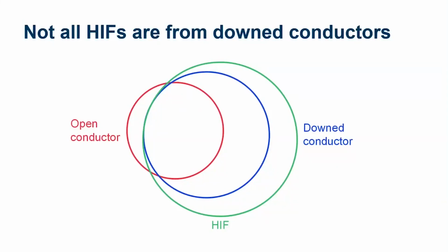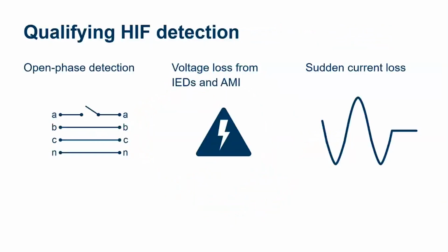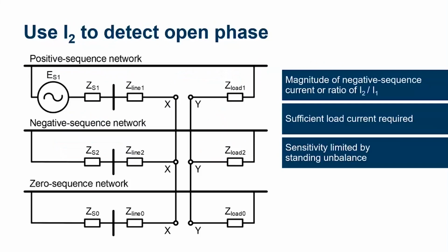So one of the things that we can do in order to give ourselves a higher degree of confidence that a high impedance fault is associated with a downed conductor is add another qualifying condition. We can look for an open phase by looking at our sequence components. We can look for an open phase condition based on voltage loss from other downstream IEDs or AMI metering, or we can look for a sudden loss of current. Let's look at a few examples here.